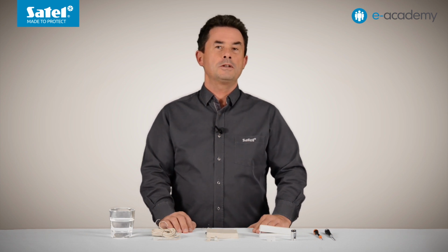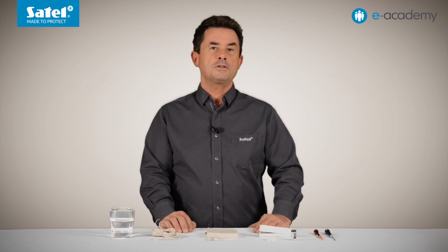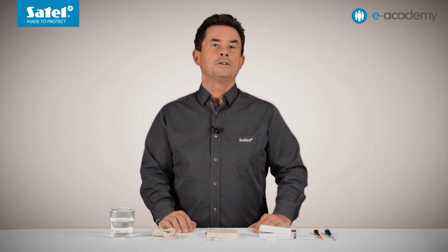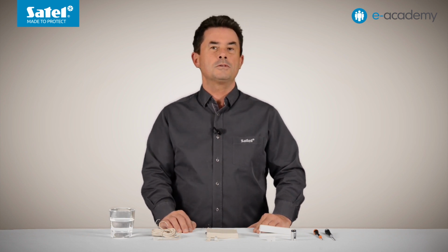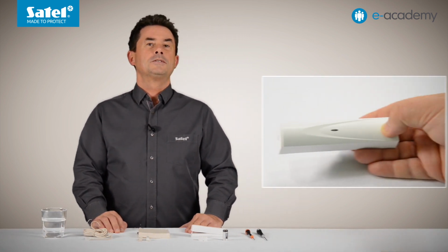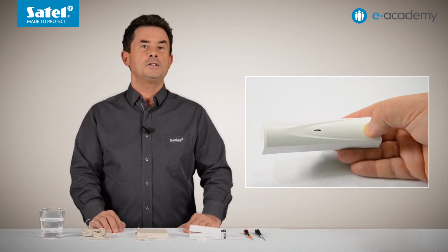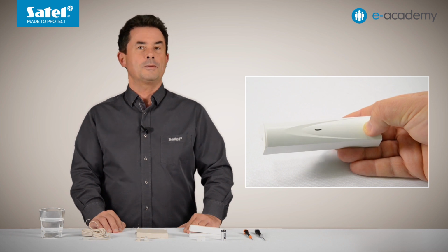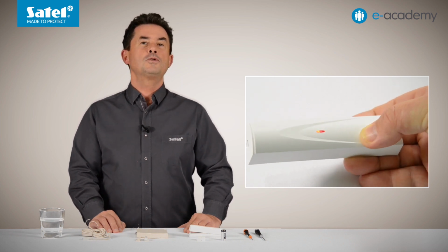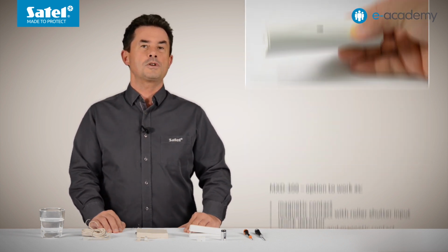OK, you already know that you can select one of the 5 functionalities for the detector. Now I will show you how to select each of them and how they work. That is, which events will be reported as an alarm. I will take advantage of that the detector works in the test mode for 20 minutes after inserting the batteries, in which the LED is on to indicate violations. So one thing at a time.